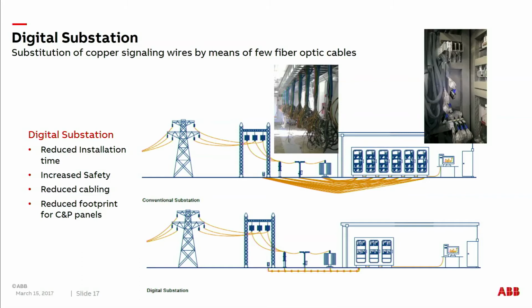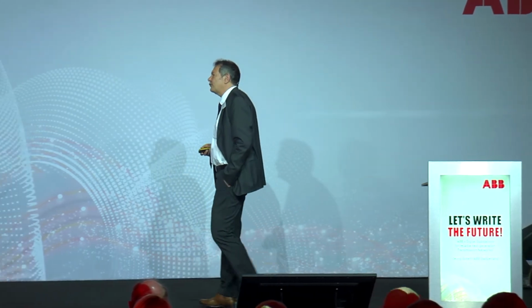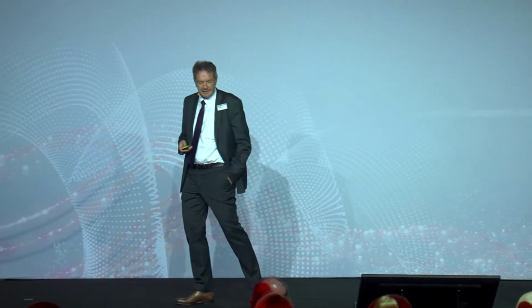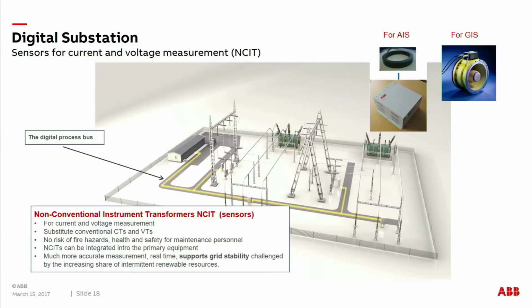The technology is starting to be ready now, and we have begun moving in that direction. With these fiber optic buses, you no longer need the bulky current and voltage transformers, the measurement transformers. You can replace them with sensors, because with these buses you can bring electronics very close to the current and voltage measurement devices, so you no longer need power output for these measurement devices.